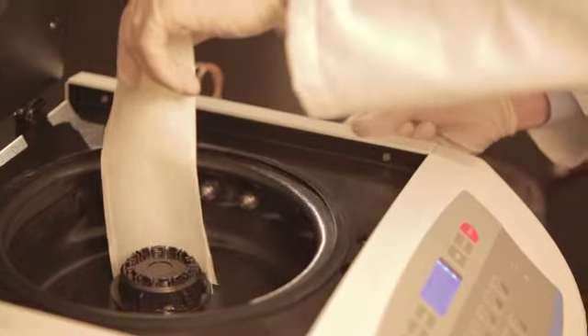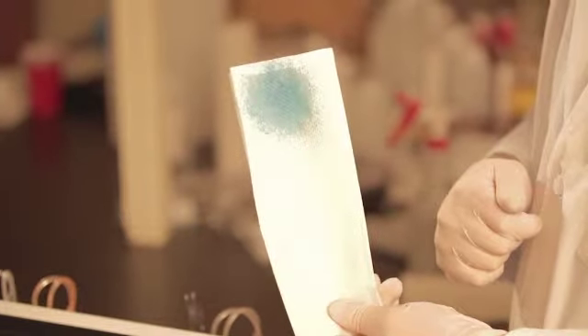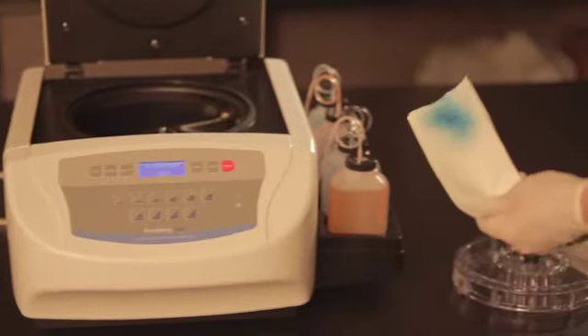Then press the prime button for the reagent nozzle being tested. A small amount of spray will come from the nozzle and onto the paper towel. The spray should be a uniform circle. If it is not, then the nozzle may be dirty and may need to be cleaned. Check the spray pattern for each nozzle.